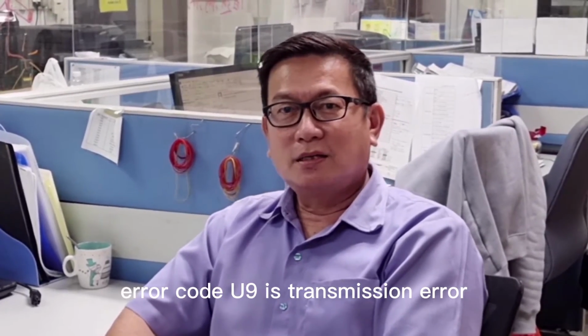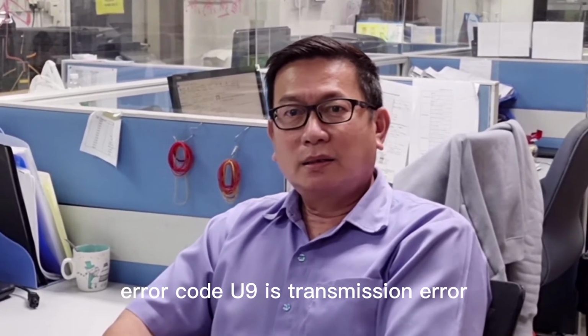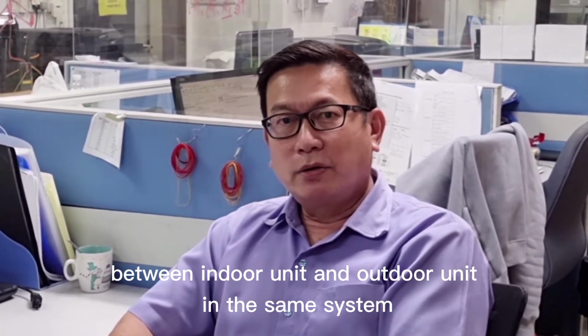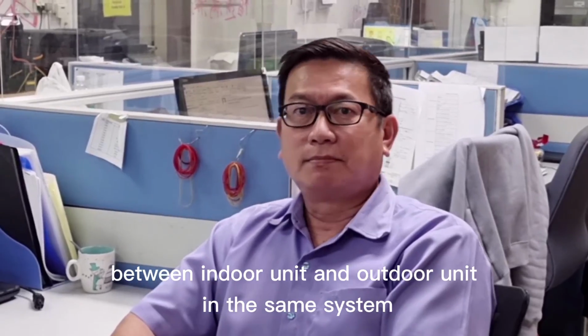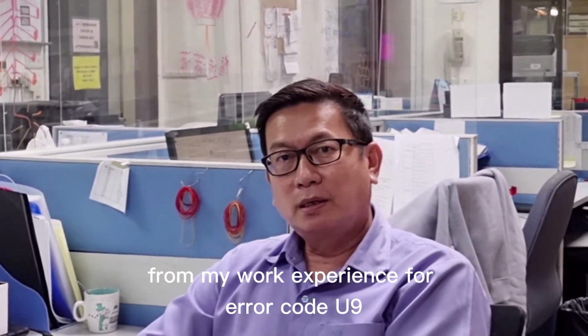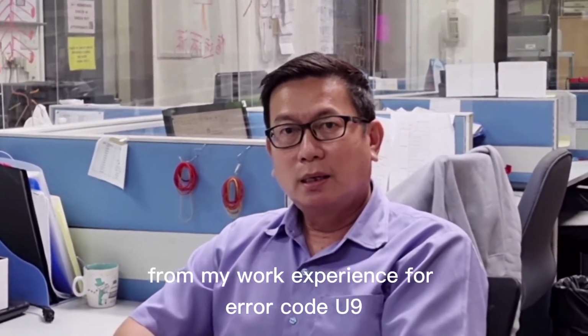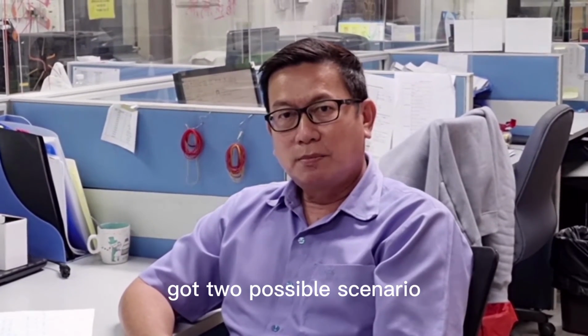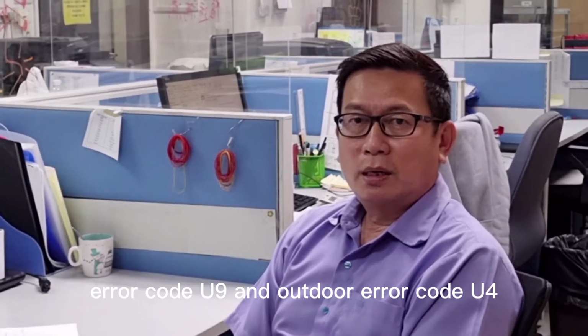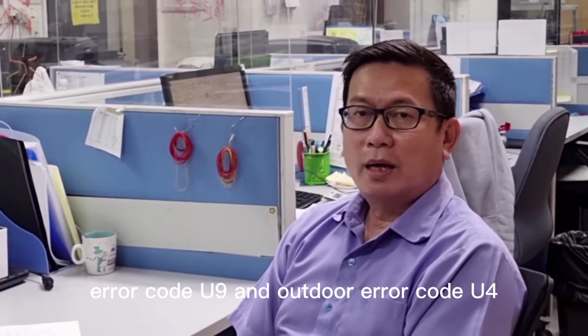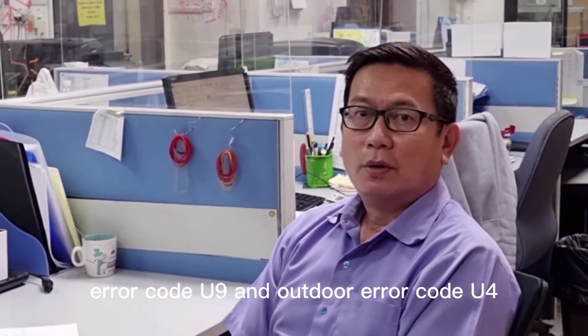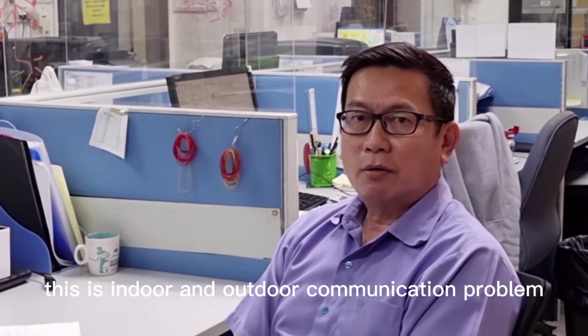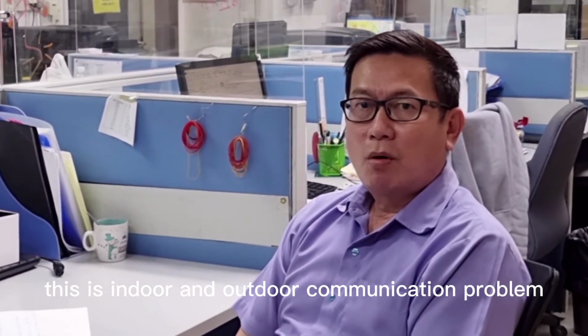Error code U9 is a transmission error between the indoor unit and outdoor unit in the same system. From my work experience with error code U9, there are two possible scenarios. First is indoor error code U9 with outdoor error code U4, which is an indoor and outdoor communication problem.